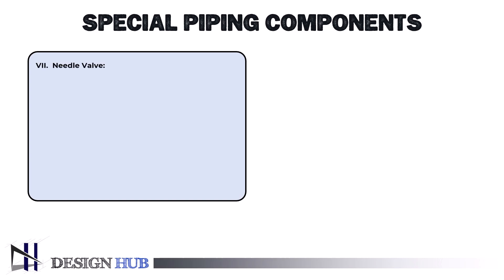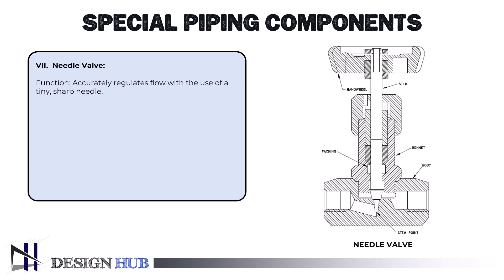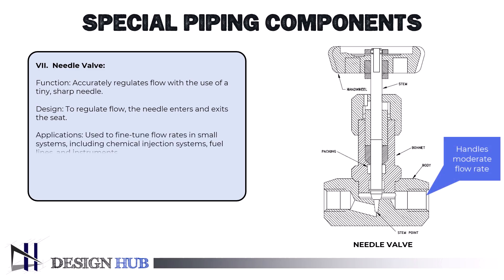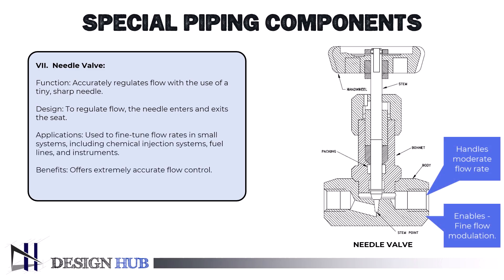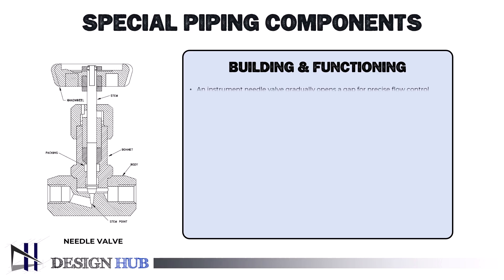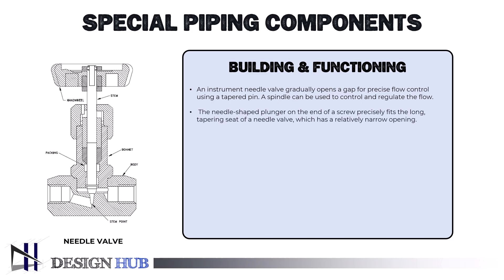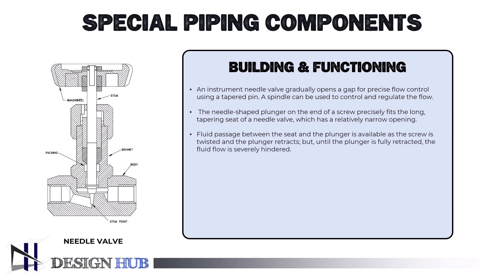The next valve we will learn about is the needle valve. A needle valve is a particular kind of valve that has a threaded plunger shaped like a needle with a tiny opening. Even though it can only handle relatively moderate flow rates, it enables fine flow modulation. An instrument needle valve gradually opens a gap for precise flow control using a tapered pin. A spindle can be used to control and regulate the flow. The needle-shaped plunger on the end of a screw precisely fits the long, tapering seat of a needle valve, which has a relatively narrow opening. Fluid passage is available as the screw is twisted and the plunger retracts, but the fluid flow is severely hindered until the plunger is fully retracted.